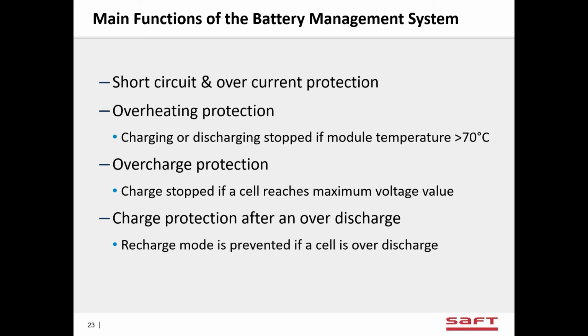Overcharge is the easiest way to push a cell into thermal runaway. So the BMS has to stop a cell from being overcharged. So our system takes control of that with the BMS. If the charger goes out of line and starts to try to charge the battery too high, we will stop the charge. And I can show you a circuit diagram of how we do that coming up. We still connect to the load for discharges if we do that.